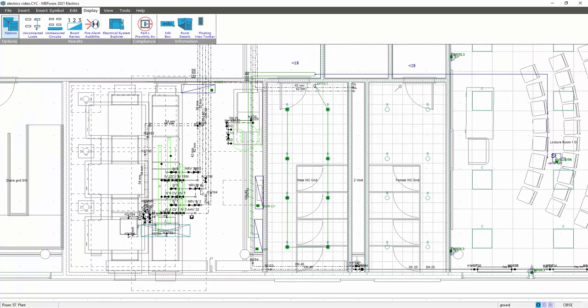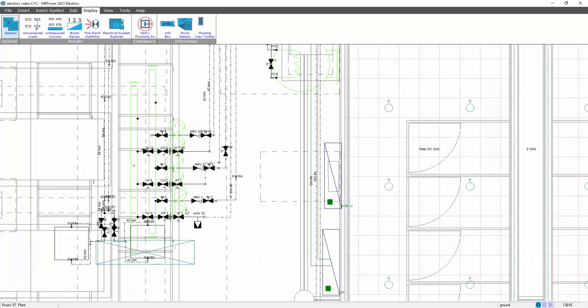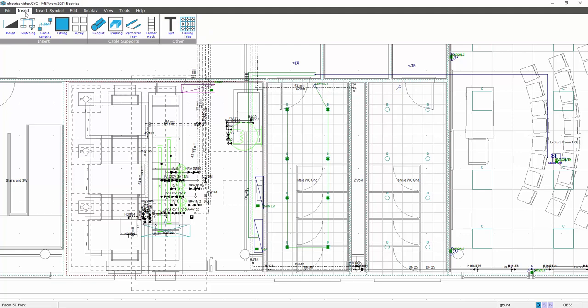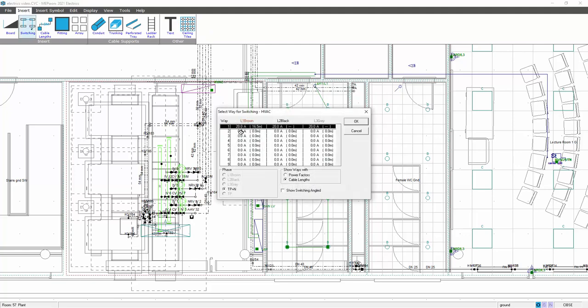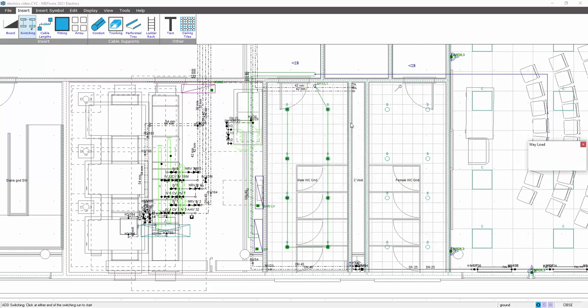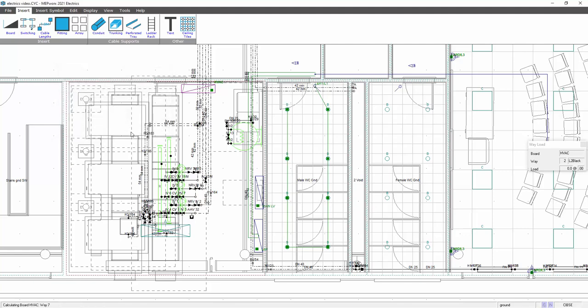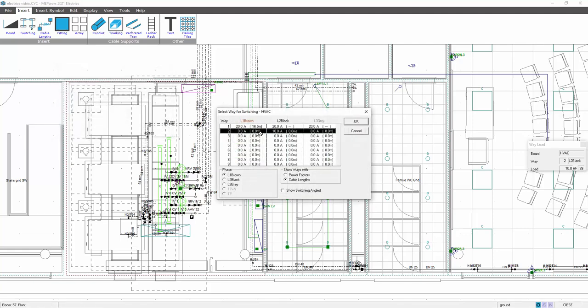So if I've got some pumps on the layout for example, I could insert some circuits on items I've already got placed. So for example, if I want to allocate one of these pumps to a specific circuit, all I need to do is insert switching. So I'll go to my HVAC board again, insert switching, and I want that pump number two on L2 black. Click on that. Double click on the pump to reveal the load. So that load was entered when the pumps were entered in the piping program. Select OK, and that then gives you a load on that particular circuit of 10 amps.